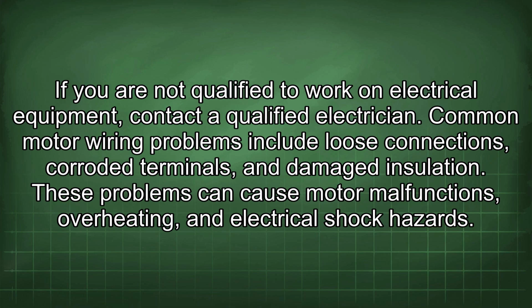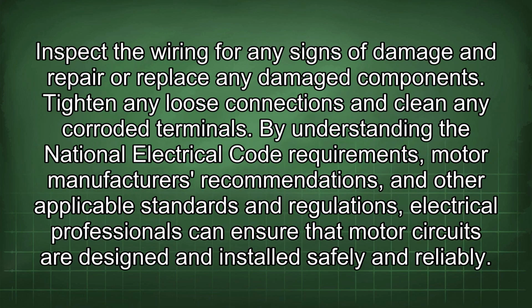Common motor wiring problems include loose connections, corroded terminals, and damaged insulation. These problems can cause motor malfunctions, overheating, and electrical shock hazards. Inspect the wiring for any signs of damage and repair or replace any damaged components. Tighten any loose connections and clean any corroded terminals.